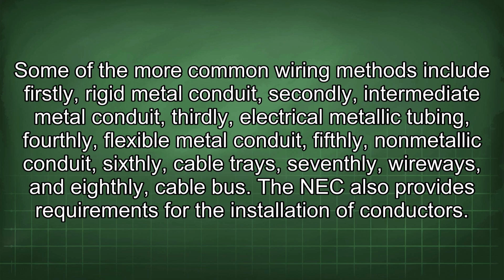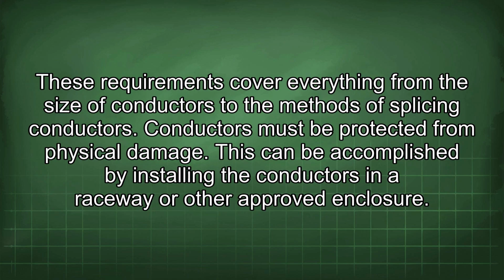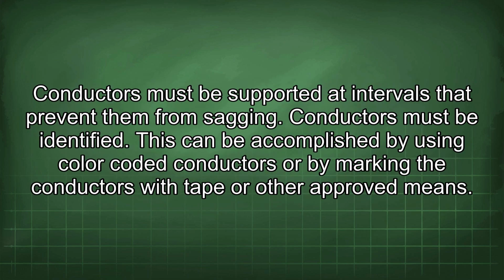The NEC also provides requirements for the installation of conductors. These requirements cover everything from the size of conductors to the methods of splicing conductors. Conductors must be protected from physical damage. This can be accomplished by installing the conductors in a raceway or other approved enclosure. Conductors must be supported at intervals that prevent them from sagging. Conductors must be identified. This can be accomplished by using color-coded conductors or by marking the conductors with tape or other approved means.